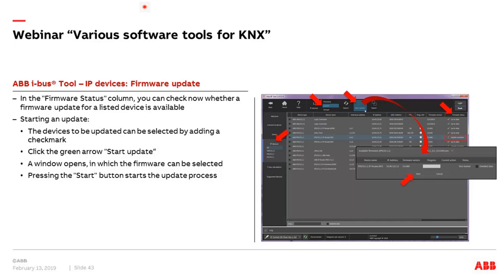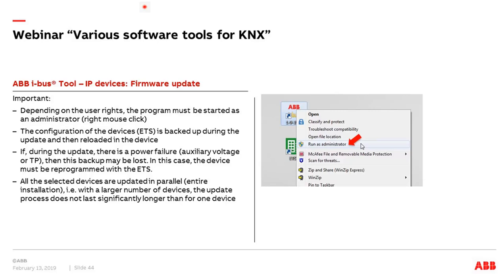You can do firmware updates in parallel since i-bus updates via the IP network, not twisted pair — so you can update several IP devices at the same time. Select all devices that need updating and press Start; the update will be done simultaneously. Sometimes you may get a failure message: 'update not possible, missing admin rights.' In that case, close the i-bus tool, right-click the icon on the desktop, and run as administrator for temporary administration rights.